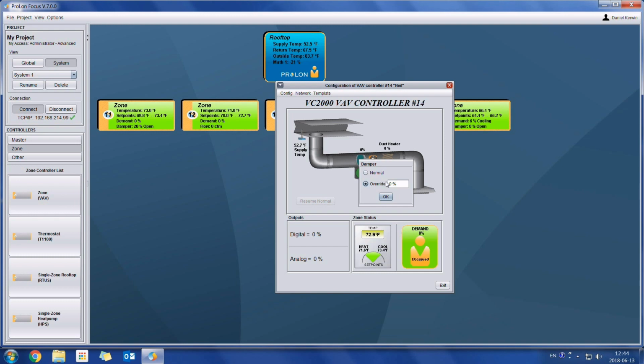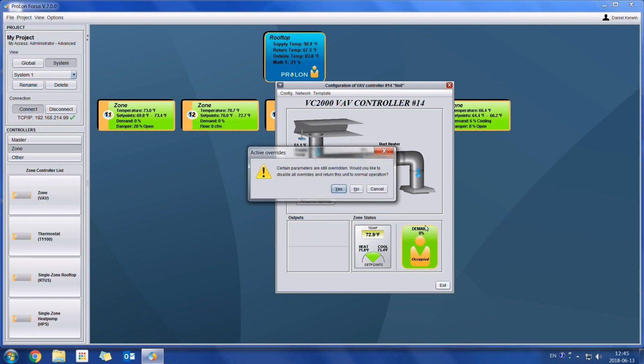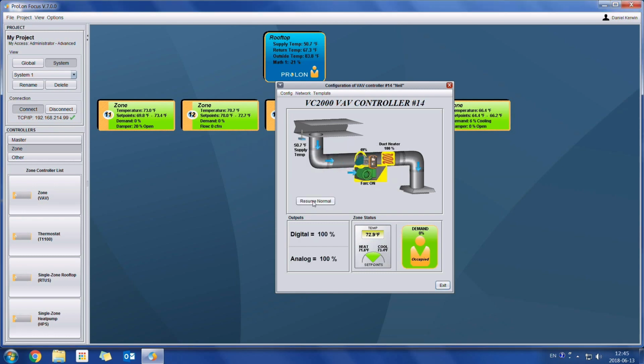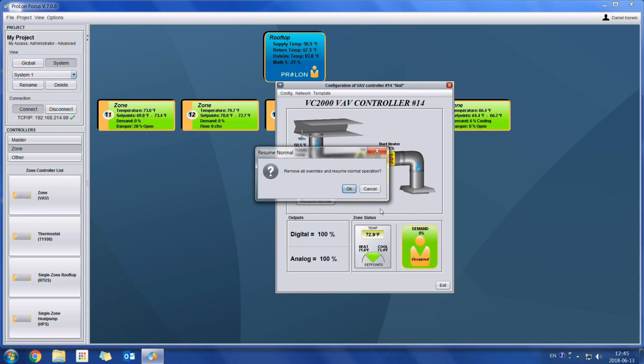So I could say override my damper to 50%. I could override my duct heater to 100%, and I could override my fan as well and turn it on. So we can see that every element which has been overridden is currently flashing in yellow, and we can also see the two outputs here are flashing as well. If ever somebody does an override and they forget to remove it and then they try to exit the controller, we do have a little warning pop-up which is going to appear so that people can't accidentally forget that they had put an override. Or I could simply click on resume normal, and that's going to remove all overrides from this controller.